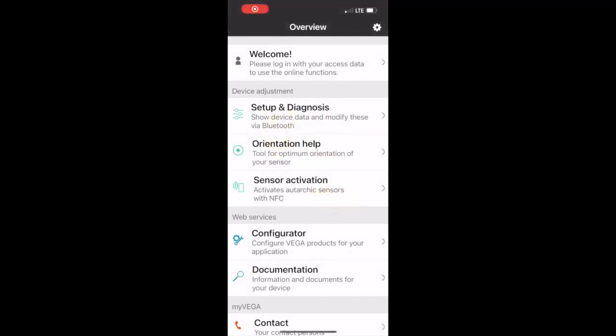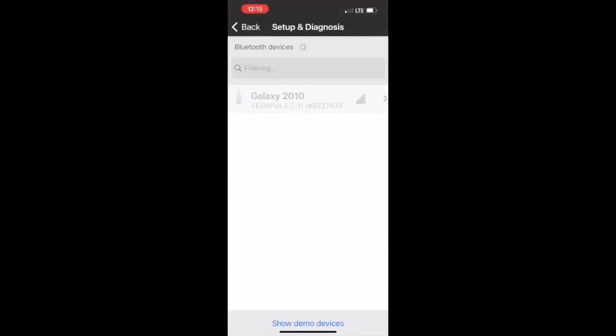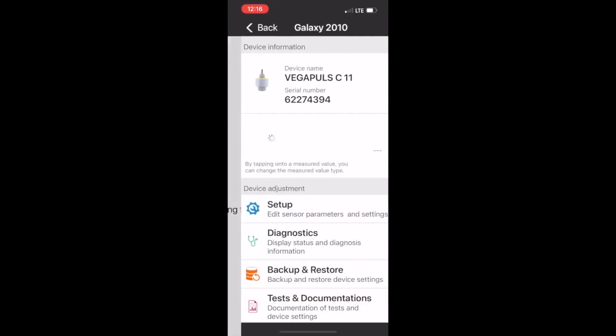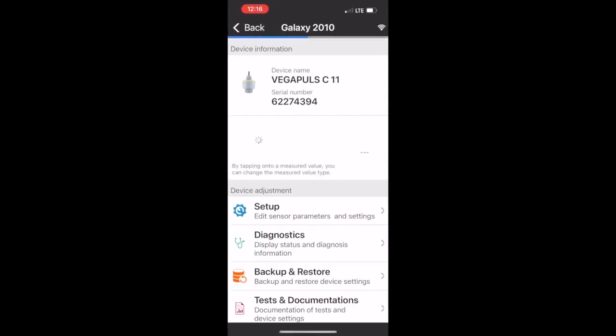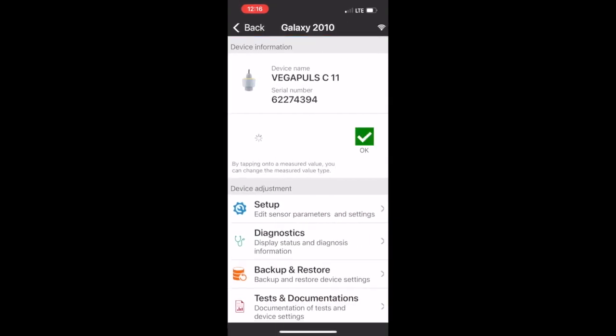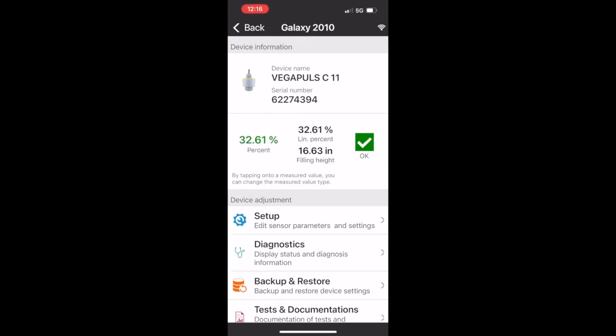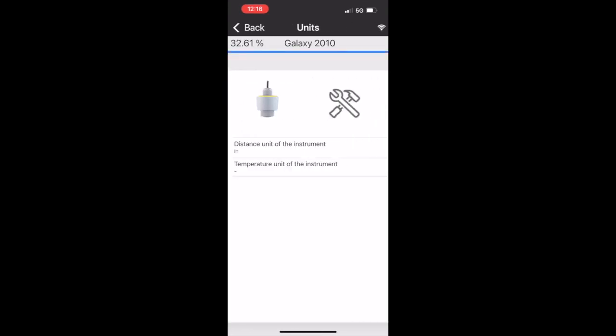If you're using a tank monitoring probe, download and open up the Vega Tools app and click Setup and Diagnostics. If the power is on, your probe should pop up. Click Connect. If this is your first time connecting, you may have to enter a code on your probe. Next, select Setup. Now, click Units and change your units to inches.